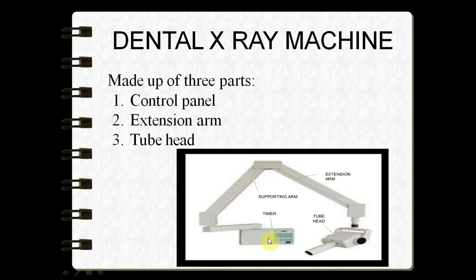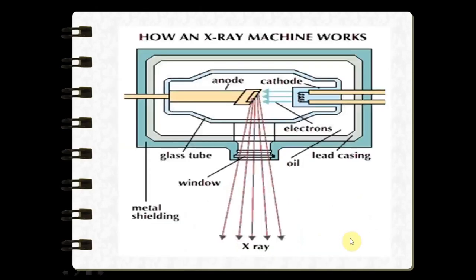The control panel also has certain control devices which regulate the x-ray beam, such as a timer which indicates the exposure time period. Then we have the extension arm, which helps suspend the x-ray tube head and also houses the electrical wires that extend from the control panel to the x-ray tube head.